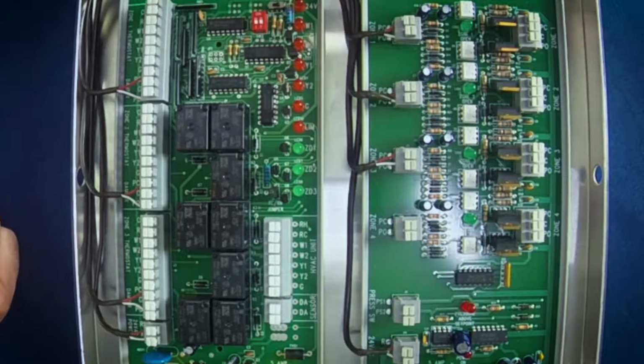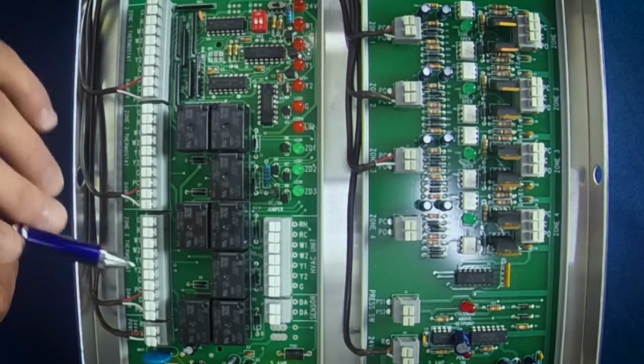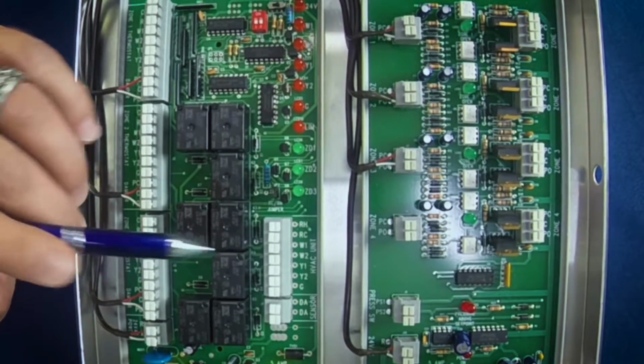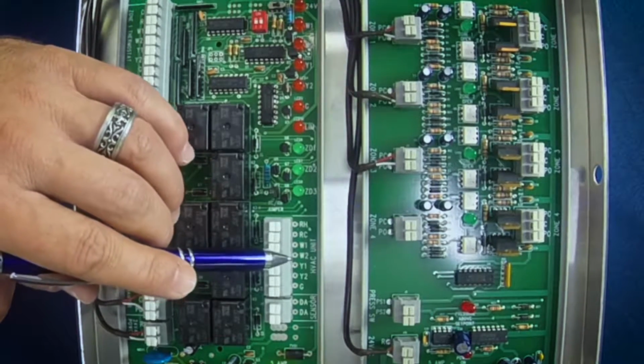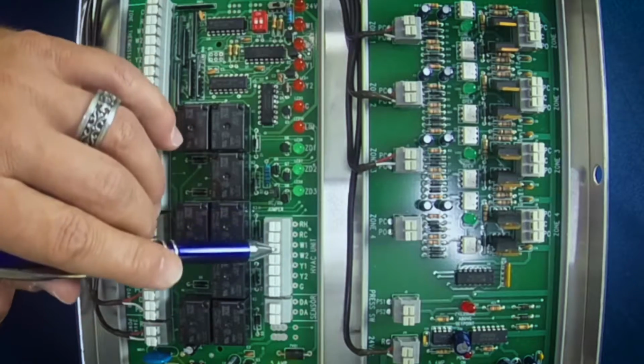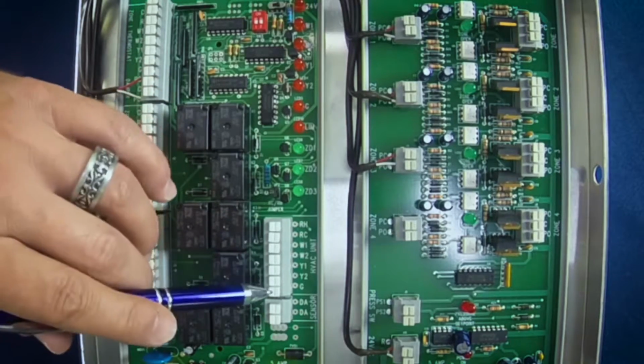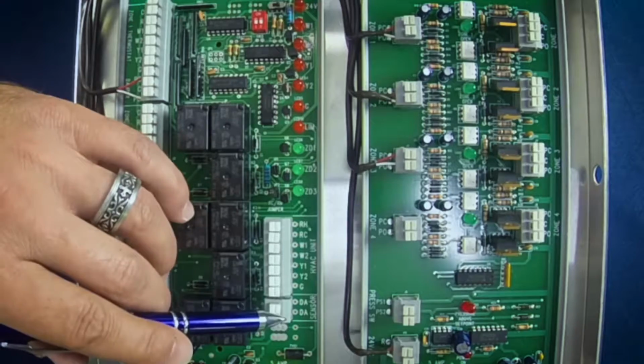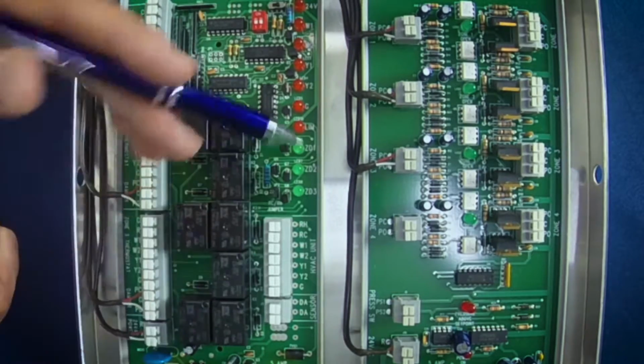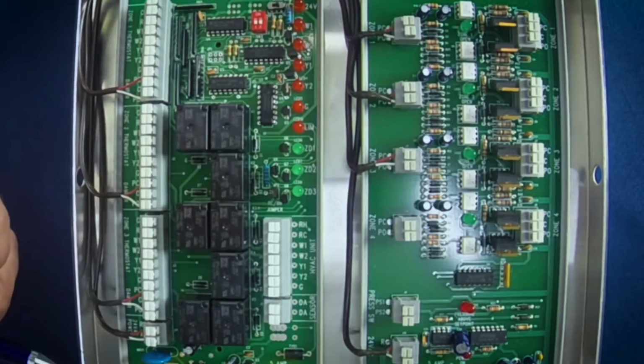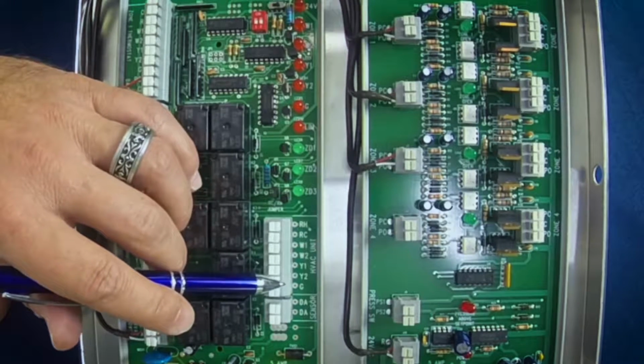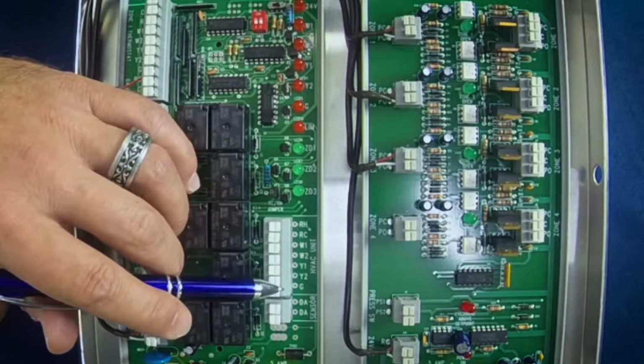Okay, now coming back over to the Z300 panel. So you've got zone 1, 2, and 3 for your thermostats. And then this is where you're going to wire in your HVAC unit. Again, your hot and your common, your first and second stage heat and cooling and fan. And obviously your discharge air sensor, and of course you'd have a reversing valve and an outside temperature sensor if this was an HP panel as well, or a heat pump panel.